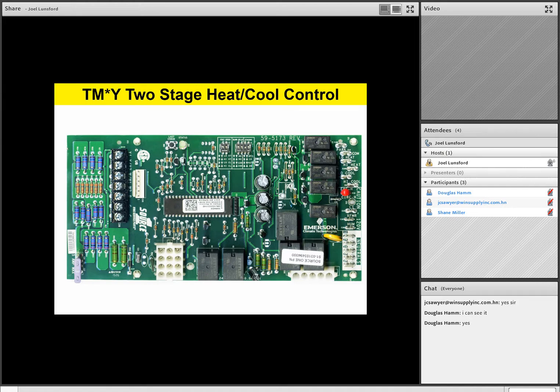But the standard ECM control board, so you're still going to have some 24-volt wires or motor taps that the technician's going to have to deal with, high heat, low heat, and so on. He'll have to select those accordingly. So this board has a Y1 and a Y2 terminal on it, as well as a W1 and W2 terminal, because it's a two-stage heat, two-stage cool control board featuring a high-efficiency ECM motor. Again, a TM9Y or a TM8Y would be the furnace products that you'd find this control board in.